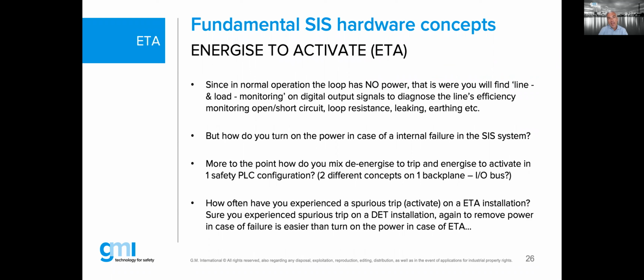Since in normal operation the loop has no power, that is where you may have, or you have seen that, or you know this already, that's where we're going to use the line monitoring. The word line monitoring means we're going to monitor the line in normal condition with no power to make sure the line is still there. Because if I go back to the de-energized and I cut the line, well, your system will lose the power and will have to go to a safe state.